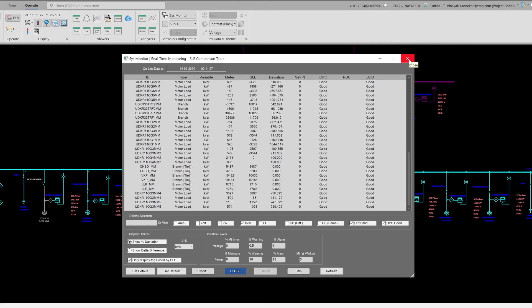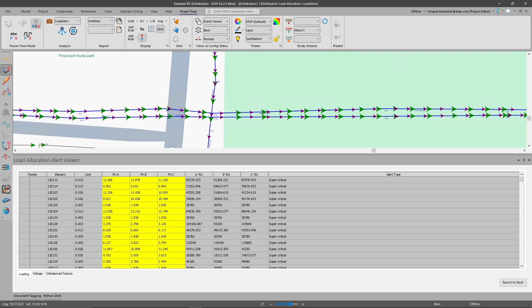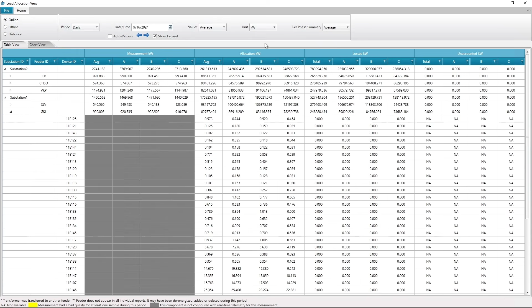Load allocation is also included, and this is crucial for understanding real-time flows and losses across the distribution network. We calculate losses, both due to heat and unaccounted for losses, which can indicate issues like theft. This data feeds into various study modules like unbalanced load flow and time domain load flow, enabling predictive simulations. You can perform what-if scenarios such as transferring loads between feeders to assess potential overloads.